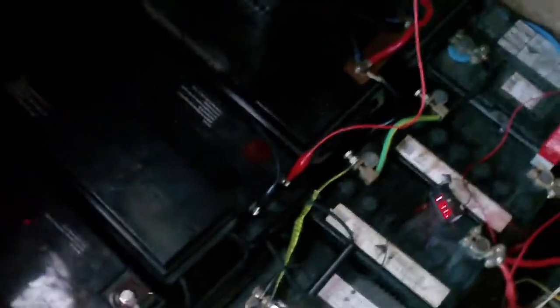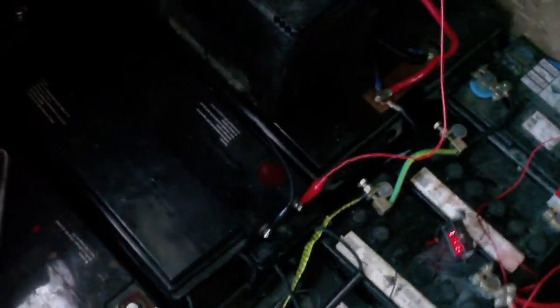What I'm actually doing here is equalizing it, so to speak. I don't mean equalizing it by charging up to a super high voltage to equalize the cells. I just mean I'm bringing this battery's voltage to the same as the others in that part of the bank so that I can unite it and it will behave well with them.